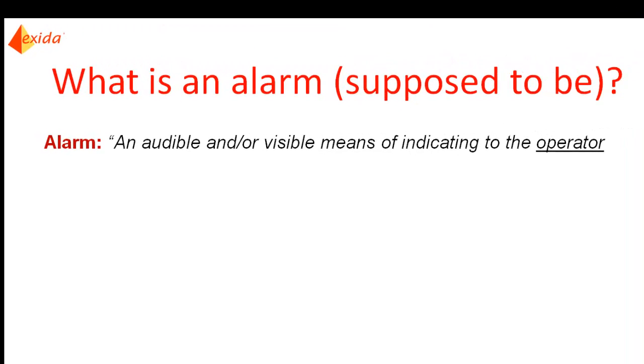Let's begin by talking about what an alarm is supposed to be. The ISA 18.2 Standard on Alarm Management defines an alarm as an audible and/or visible means of indicating to the operator. Notice the emphasis on operator — the target of the alarm system is the operator, not the process control engineer or maintenance technician.